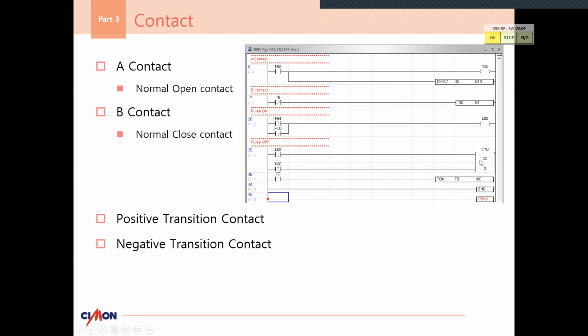When this function has counted up to 3, C0 will ignite. It will become a 1. Typically, what people do to reset counters is make the variable that is counting up be the reset. So people will put a C0 right here, and once you've hit 3, it will energize down here, but it will also reset the counter for you. When C0 has been powered, it will turn the timer on and start counting to 100 ticks. T0 is counting 1 tick per 100 milliseconds. So 100 milliseconds times 100 would be 10,000 milliseconds, which puts us at 10 seconds. After 10 seconds, this will fire. This will energize itself, and T0 will become a 1. We talked about T0 before. So when T0 becomes a 1, this stops executing, and then D1 would stop increasing.